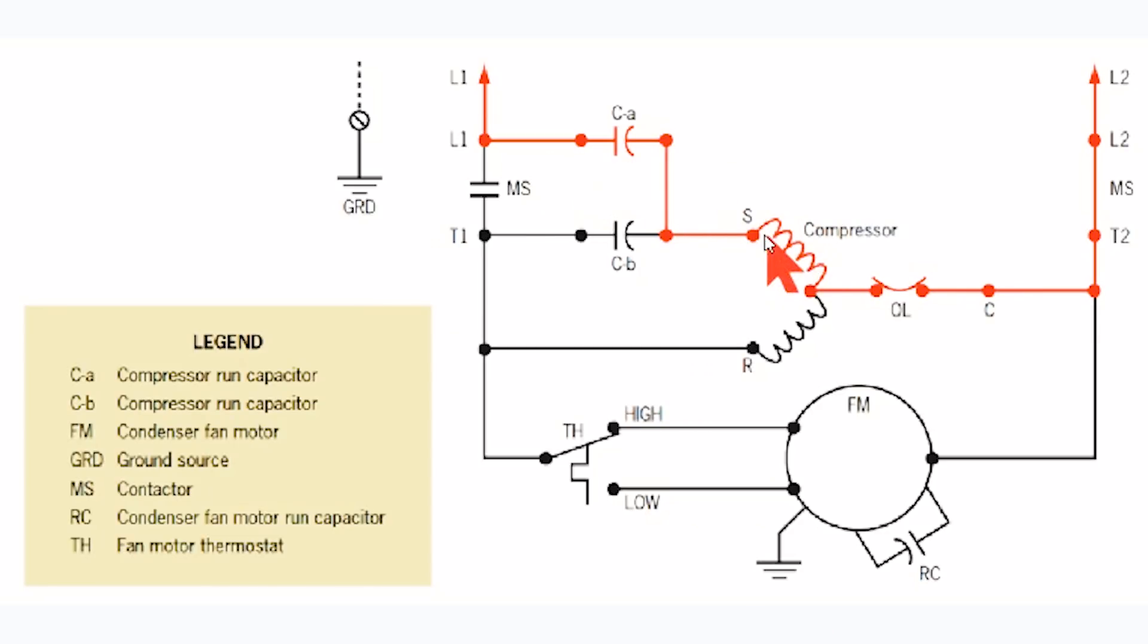It allows a small amount of current to still move through this start winding. What does the start winding become? It becomes a heater. When you have a motor that's running locked rotor and it can't turn, those motor windings become a heater. In this case, the start winding is becoming a heater.